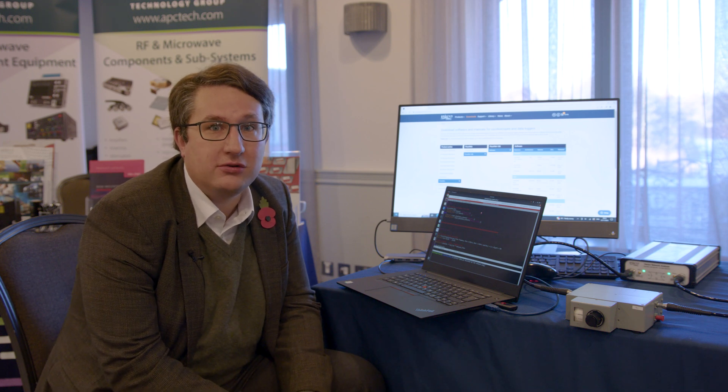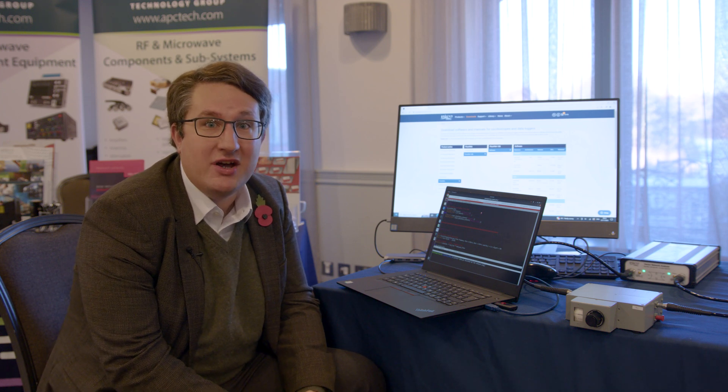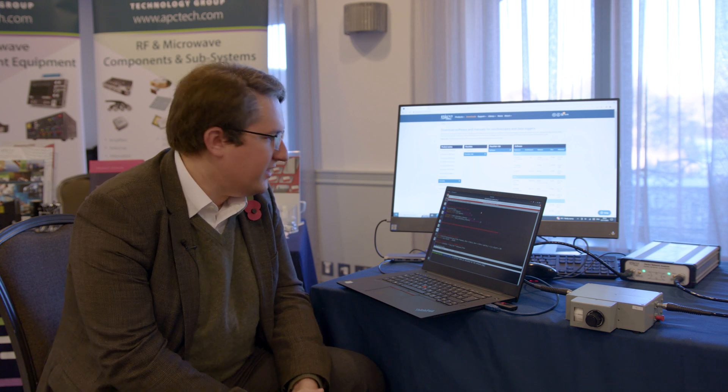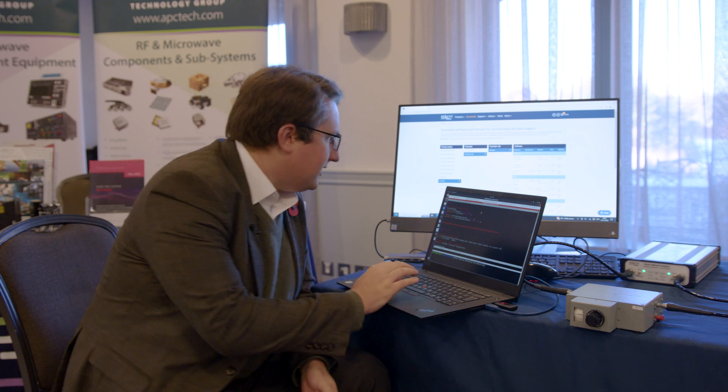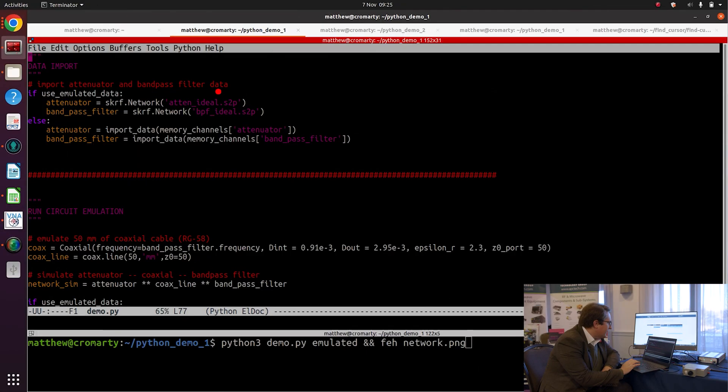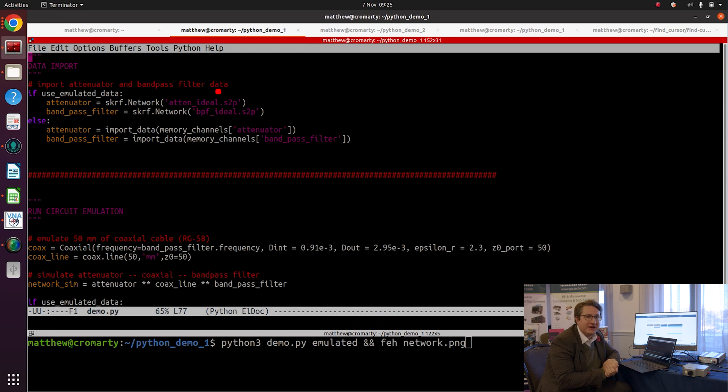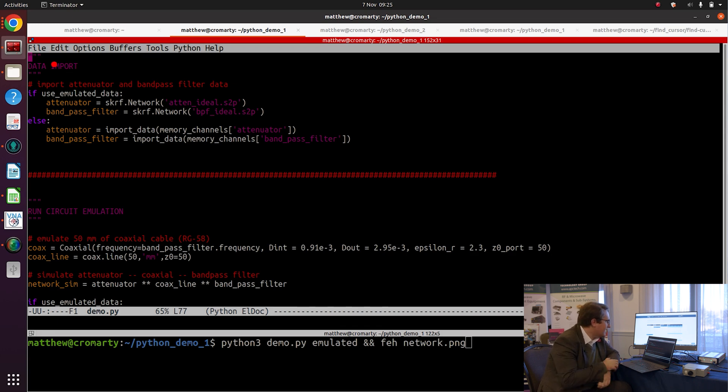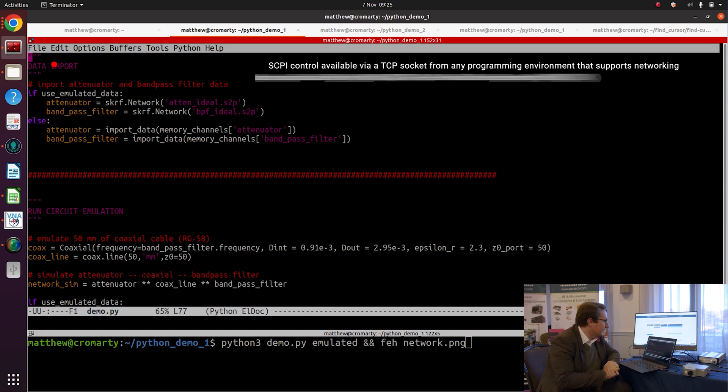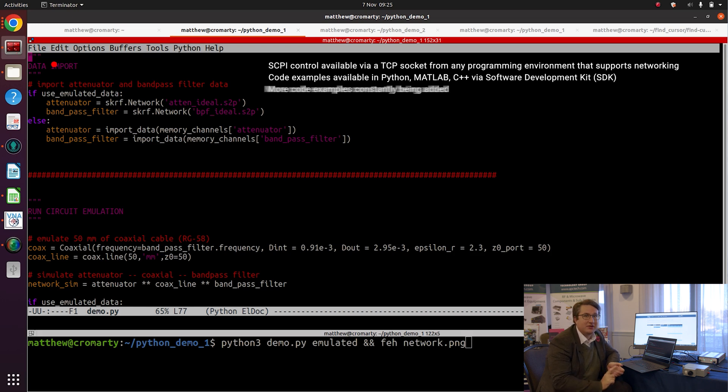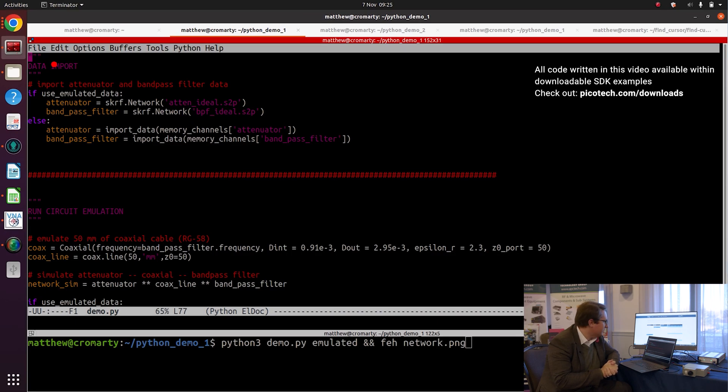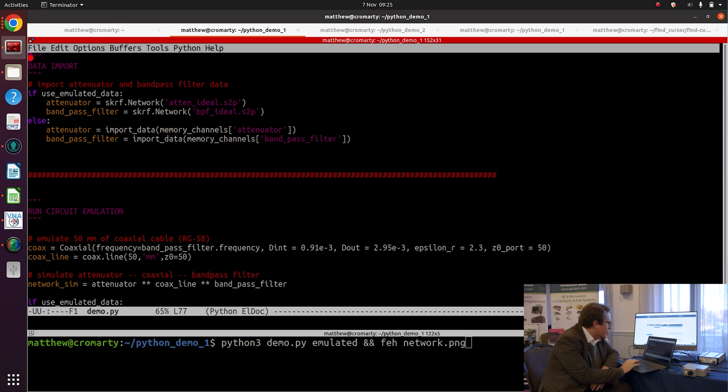We're going to be concentrating on remotely controlling the PicoVNA 5 software via SCPI. Let's have a look at what we'll be doing. I'm not going to start with the PicoVNA 5 software, I'm going to start with the application I've written to remotely control PicoVNA 5 via SCPI. This application is written in Python, but equally I could be controlling PicoVNA 5 remotely from MATLAB, from LabVIEW, Simulink, or the programming environment of your choice.